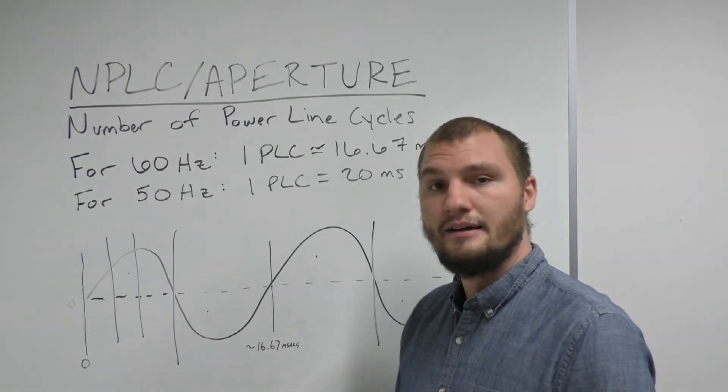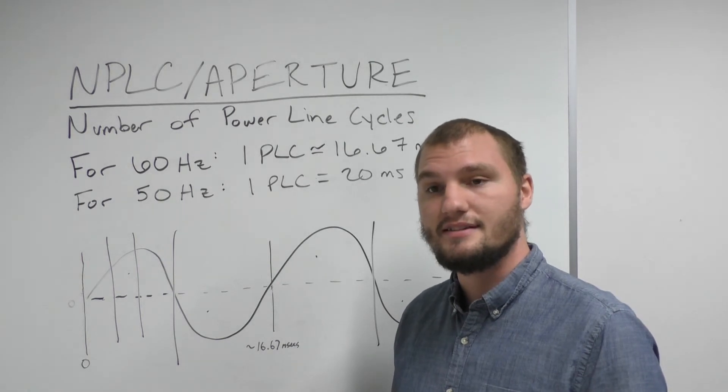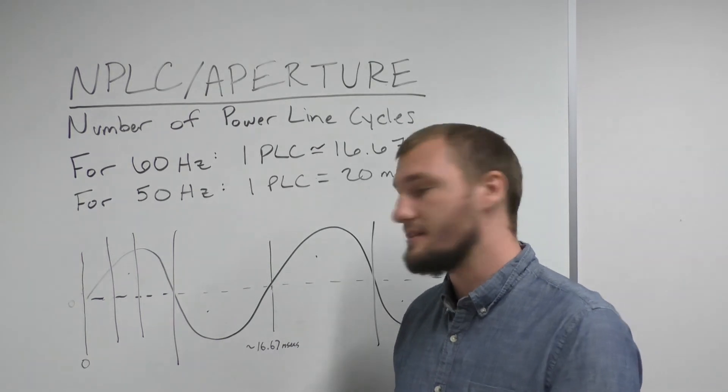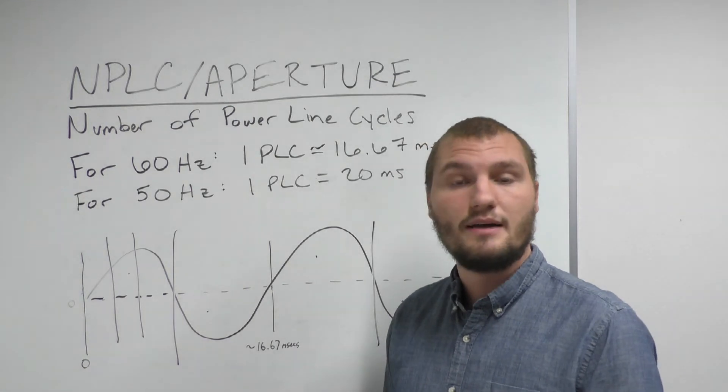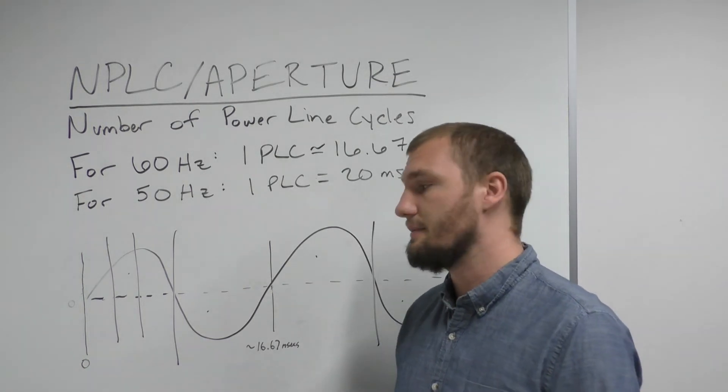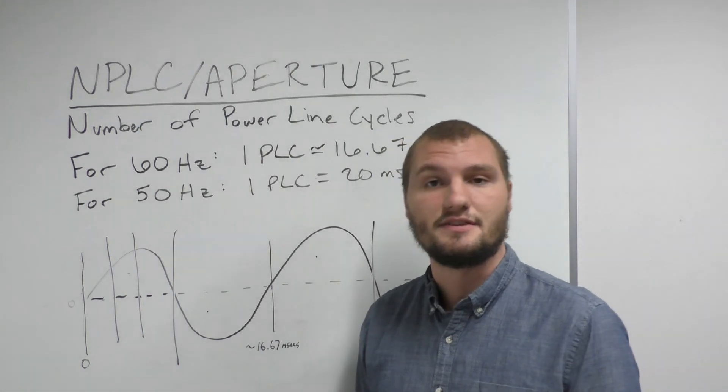But the basic takeaway from all of this is that if you want very fast measurements set your PLC as low as possible. If you want very quiet measurements set it as high as possible. Typically we recommend about five or six so that you still have some speed left.